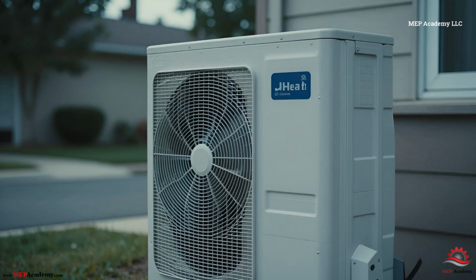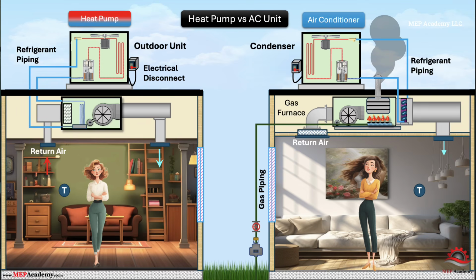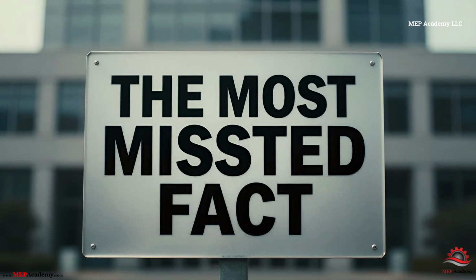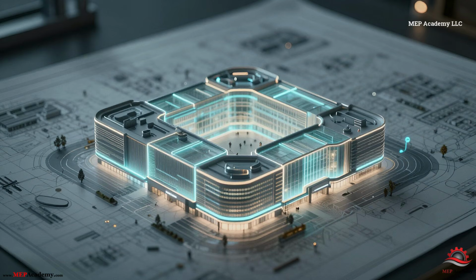Heat pumps usually have higher upfront cost and possibly lower energy bills in mild climates. Air conditioner plus furnace are often lower first cost and can be cheaper operating where natural gas is inexpensive. The most missed fact. Now here's where most HVAC decisions go wrong. System selection should not be based on the building alone. It should consider zone loads.